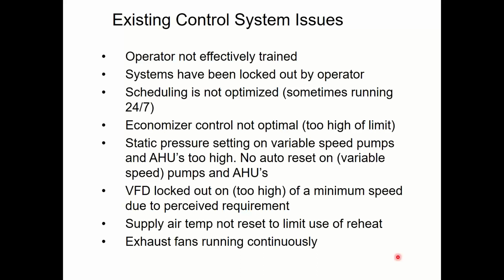Economizer set points are always wrong, every time. Every job, they're always wrong. We'll go through that in detail, but for right now, just believe me that the economizers are set up wrong or disabled. For variable speed fans and variable speed pumps, the static pressure setting, which is how we control those types of variable devices, is set up wrong almost every time.